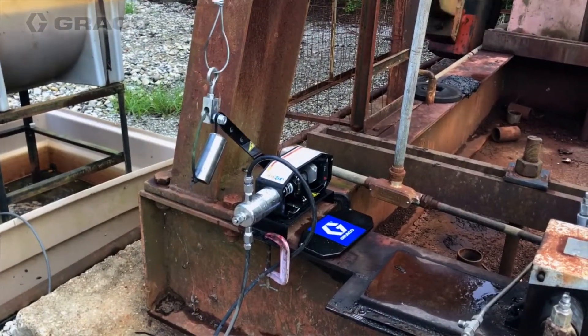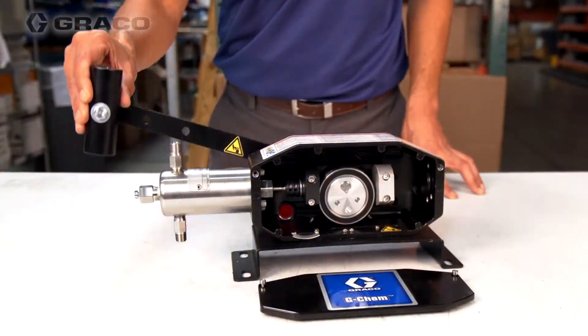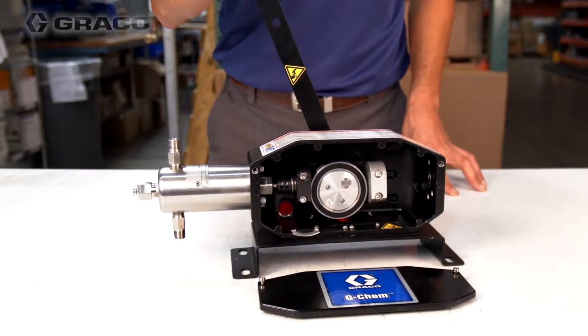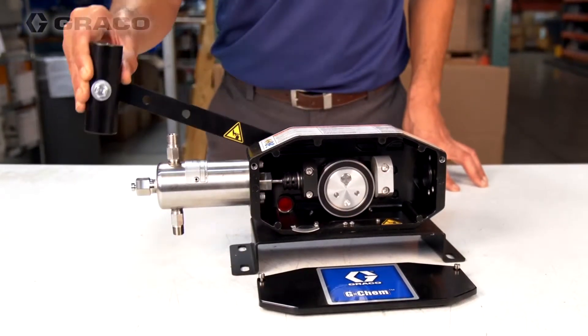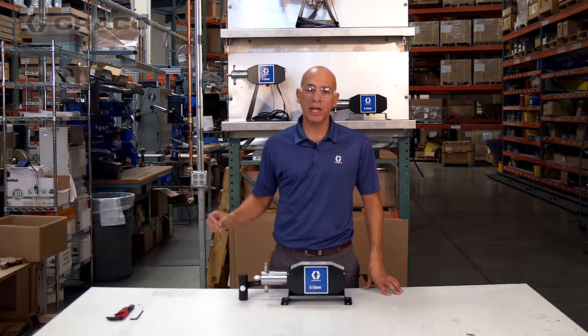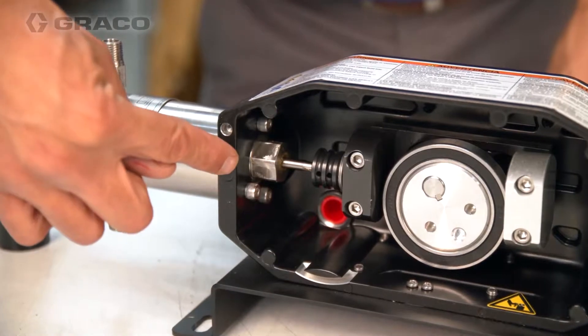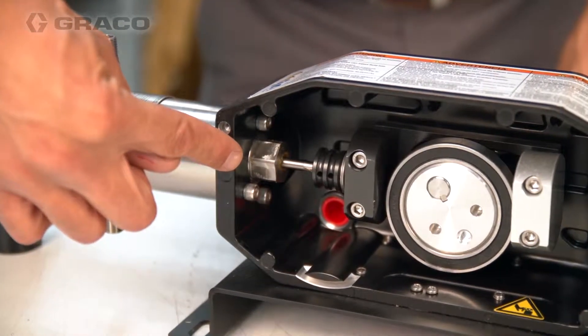It features a rocking cam design that ensures immediate chemical dosing as soon as the arm starts to move in the upstroke position. Because of this, the GChem beam pump covers a wider range of flow than most similar competitive pumps, plus helps with pump efficiencies.